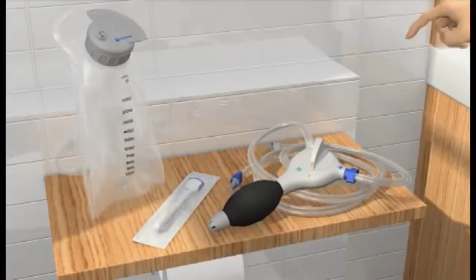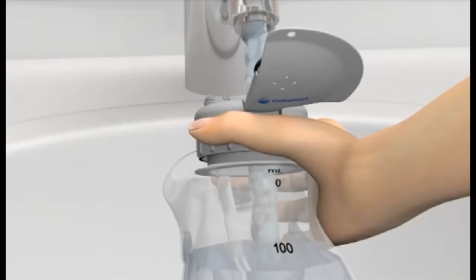Start by filling the water bag. The water must be at body temperature. If it's too hot, it may harm the delicate lining of the bowels. If it's too cold, it may cause cramps. To properly read the volume scale on the bag, you need to fill the bag completely, even though you will not use all the water for your irrigation. Make sure you have closed the lid properly. Place the water bag on the floor or another suitable place near to where you will carry out the irrigation.